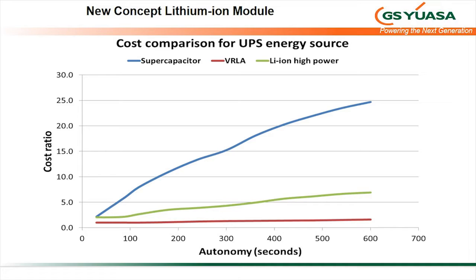And lead acid, this is where it's the incumbent, and there's good reasons for that, because we are talking, even out at 10 minutes, two or three times, and costs are coming down for lithium, but you're still talking two or three times. If you just want a straightforward 10-minute backup, not used very little, once or twice a year when there's a blackout, or you want to test it for a period, lead acid, VRLA, is going to be there for a long time to come. So we certainly don't see it as taking over for the traditional applications.